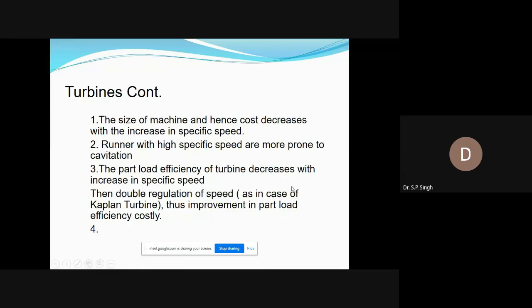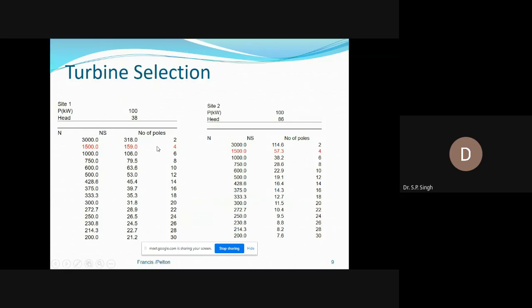Let me come back again to how we are going to select a turbine. The basic issue depends upon the head. Let me take an example of a site having a capacity of 100 kilowatt, with a head of 38 meter. Let me choose the speed of the rotor, the speed number and the synchronous speed, and then the specific speed, from the application chart provided by the manufacturers of the turbine. Let me pick up a generator of 1500 RPM having 4 poles. This may be one of the options.